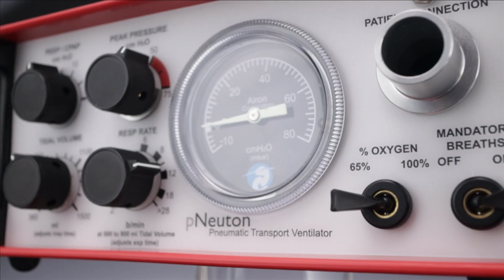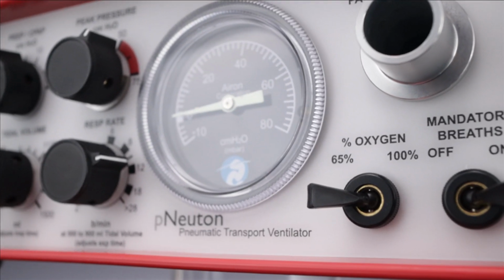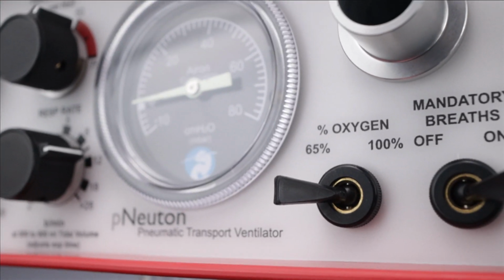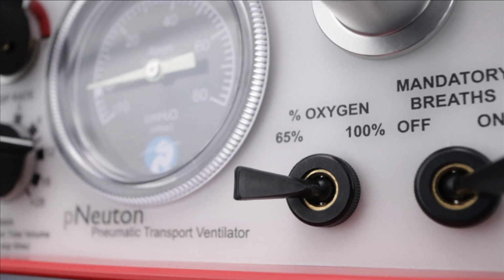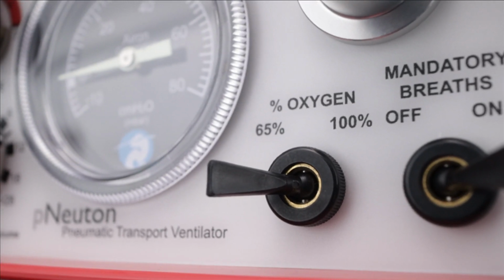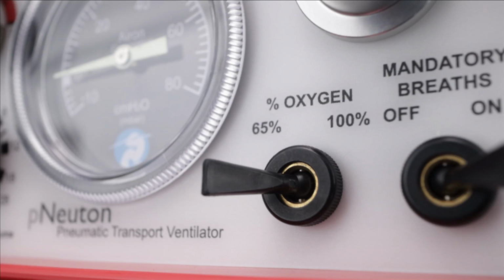To the lower right of the manometer is the percent oxygen control switch. With the ventilator driven by 100% oxygen as the source gas, the Model S's variable oxygen control system allows the clinician to choose either 65 or 100%. Both mandatory and spontaneous breaths are delivered at the set oxygen level.